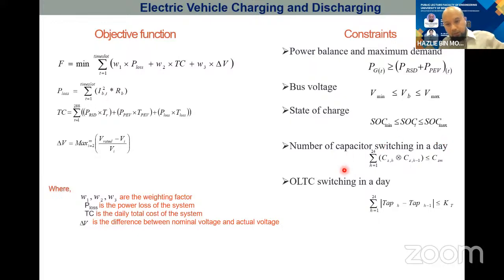In this work we go a little more advanced - we look at capacitor switching in a day, how many capacitors need to be switched to support the charging, and also the on-load tap changer (OLTC) switching in a day. There's a maximum number allowable, so this becomes a constraint, and also how many times the OLTC will be changed is also a constraint - we cannot exceed that, because it would disturb the system.